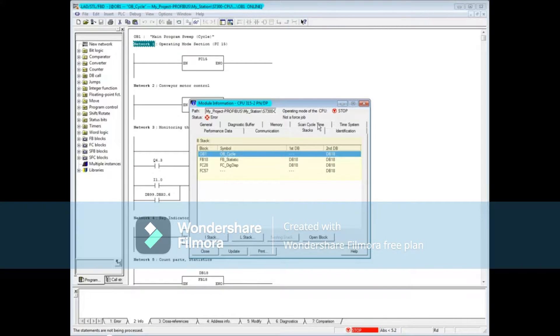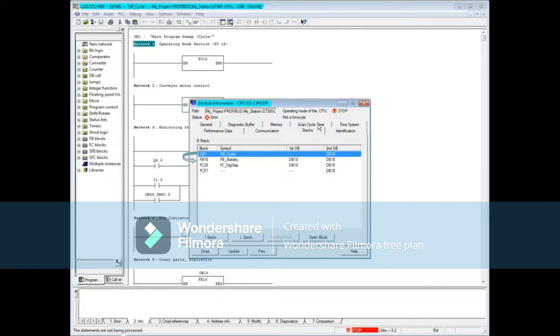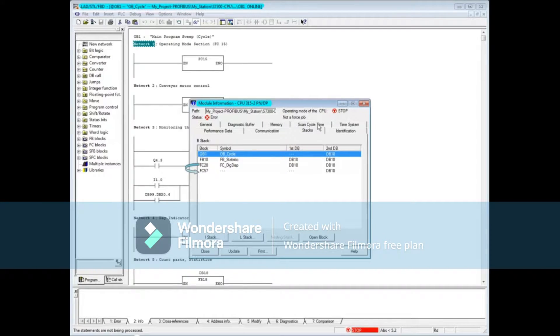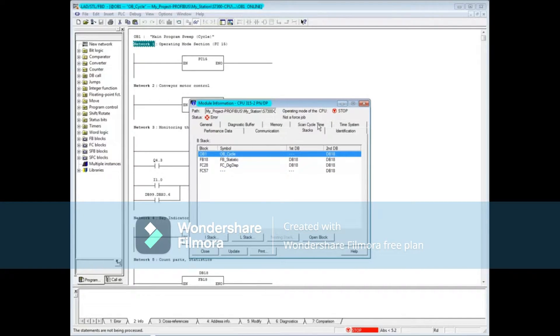What this shows is the calling order up to the fault interruption. This view shows that OB1 called FB18, FB18 called FC28, FC28 called FC57, and whatever fault occurred is in FC57. You can also see if any data blocks were open during the block calls.